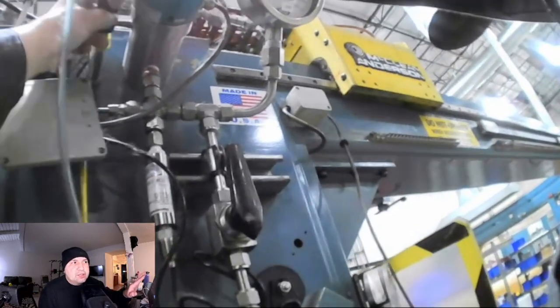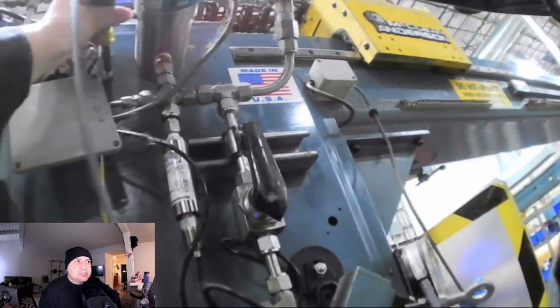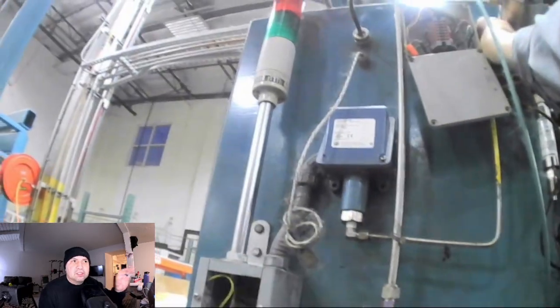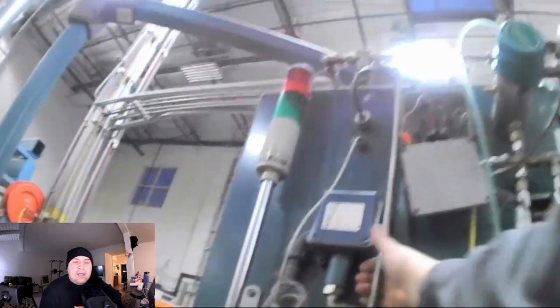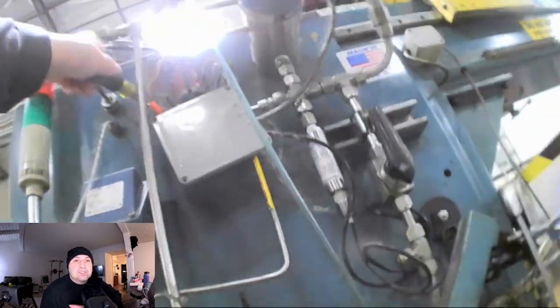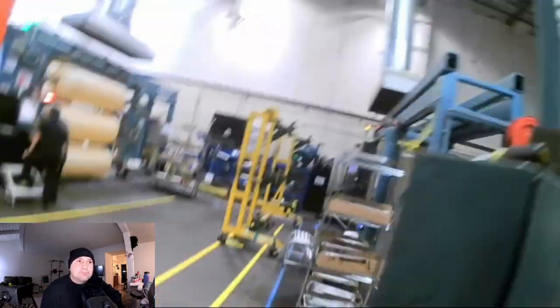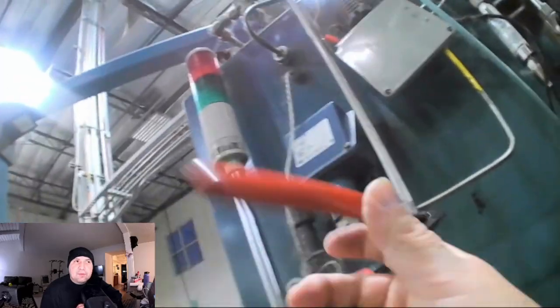I'm removing the other junction box that holds all the communication terminal blocks. Those terminal blocks are about 20 gauge wire, for all the low voltage communication, carrying all the milliamp signals that go in and out of that Tescom unit.